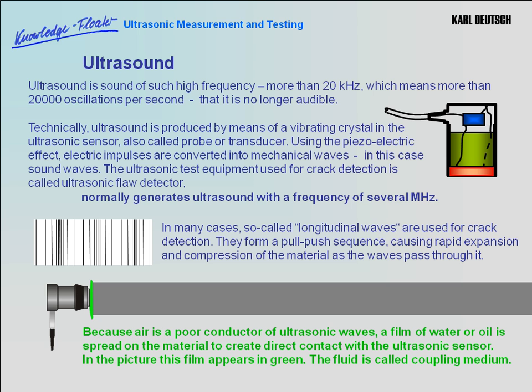Because air is a poor conductor of ultrasonic waves, a film of water or oil is spread on the material to create direct contact with the ultrasonic sensor. In the picture, this film appears in green. The fluid is called coupling medium.